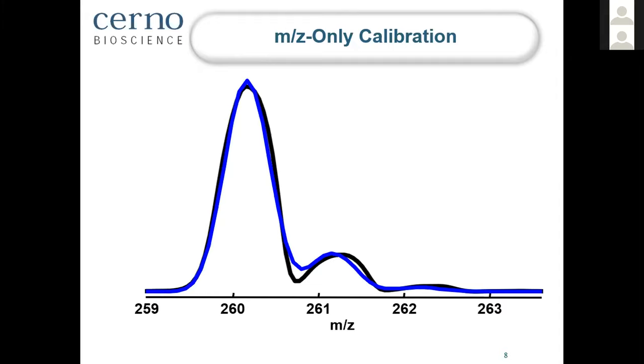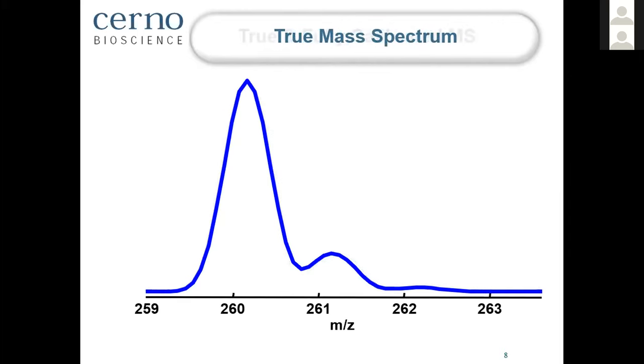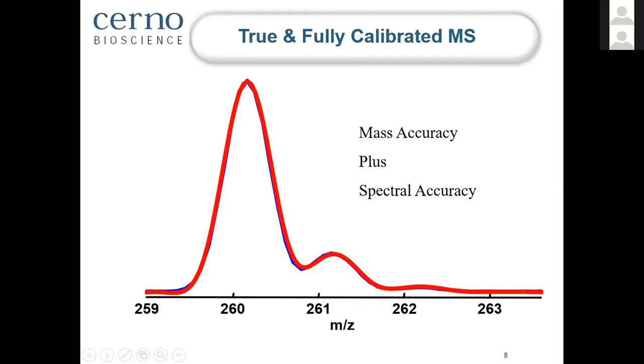So we had to come up with a different approach to perform the calibration, which can, using the same experiment, using the same standard even, but performing the calibration differently, so that after calibration, we produce a red trace that can be superimposed quantitatively on top of the theoretical mass spec. And thereby we calibrate both the mass error, in terms of the X location, and also the peak shape, so that after calibration, the calibrated mass spec would be quantitatively accurate compared to the theoretical mass spec on a full spectral profile mode basis.